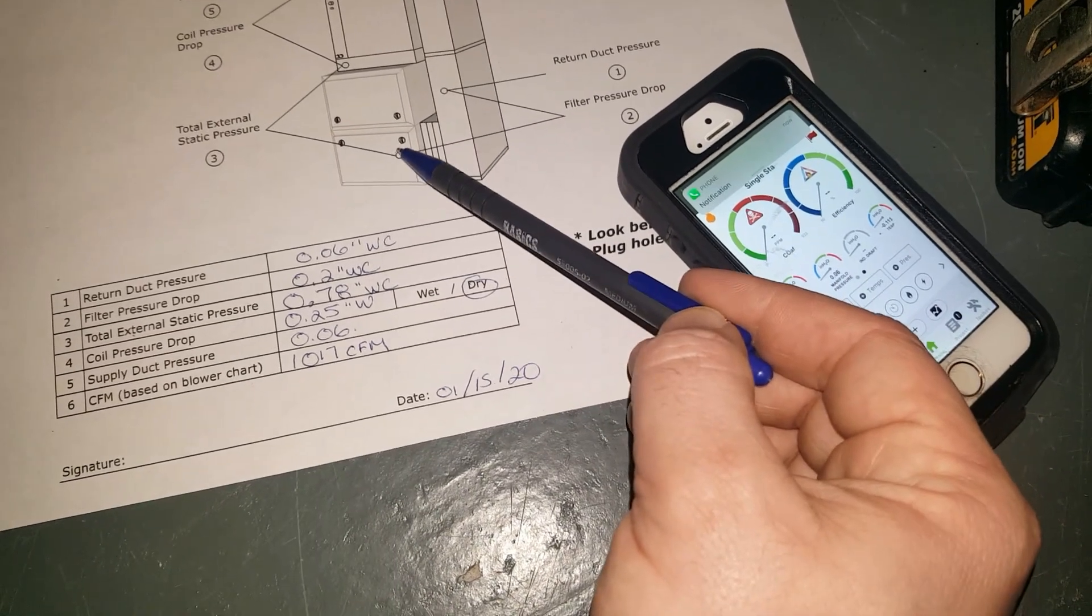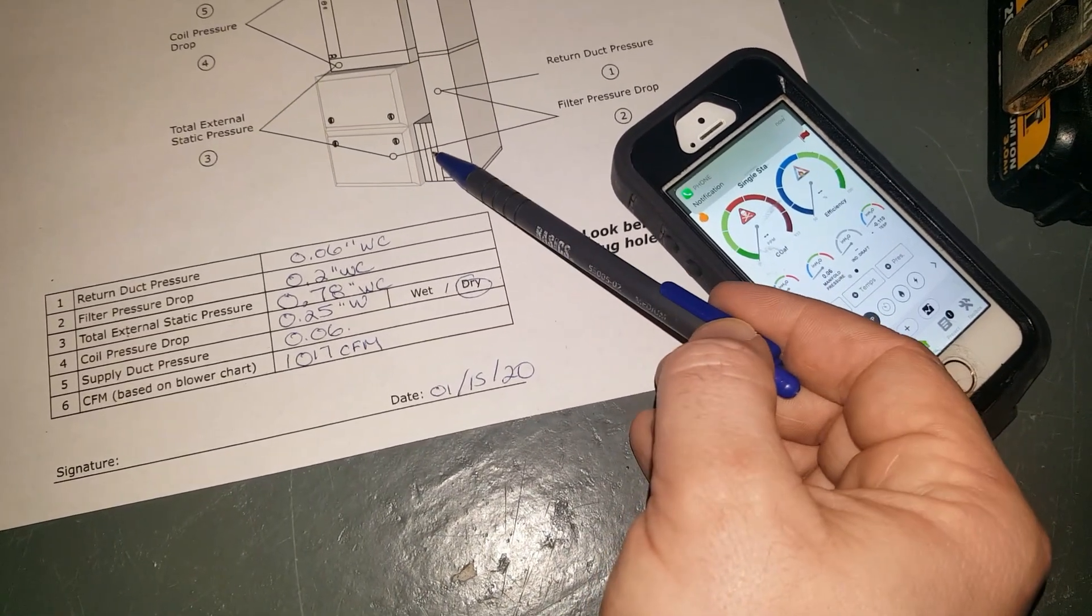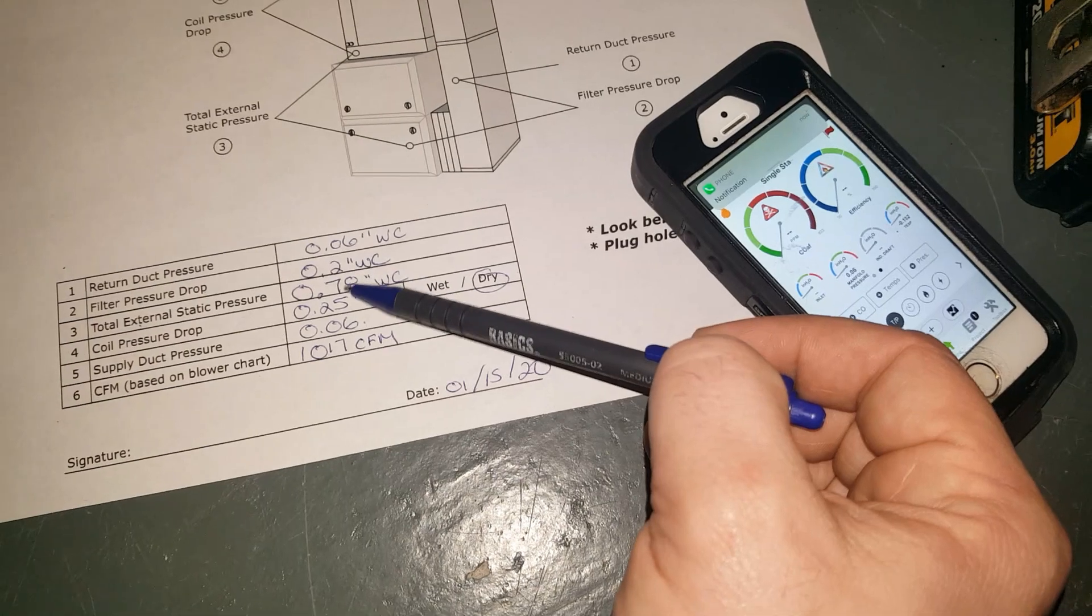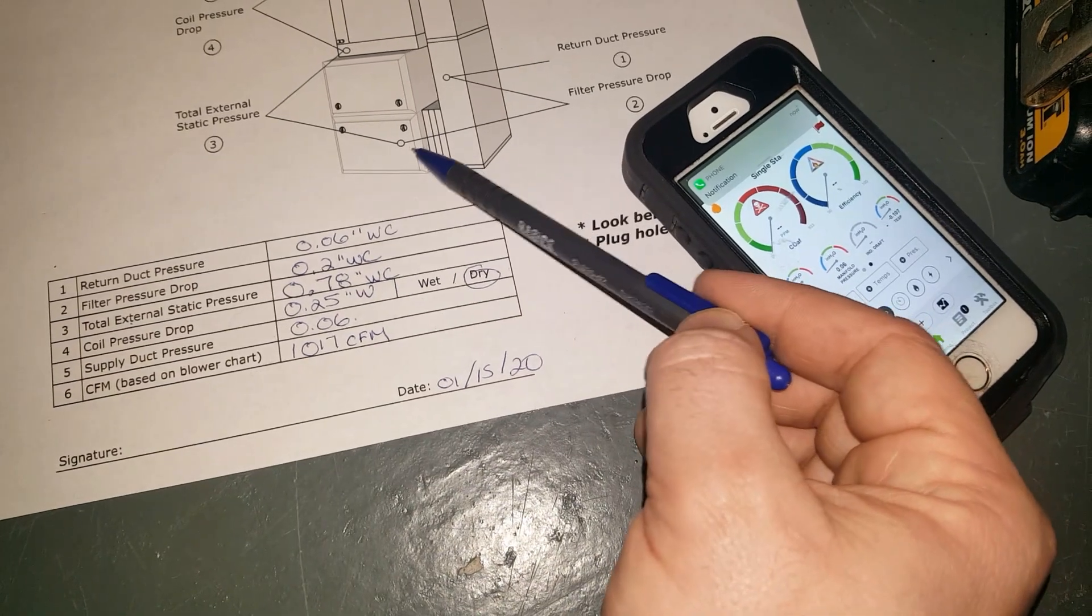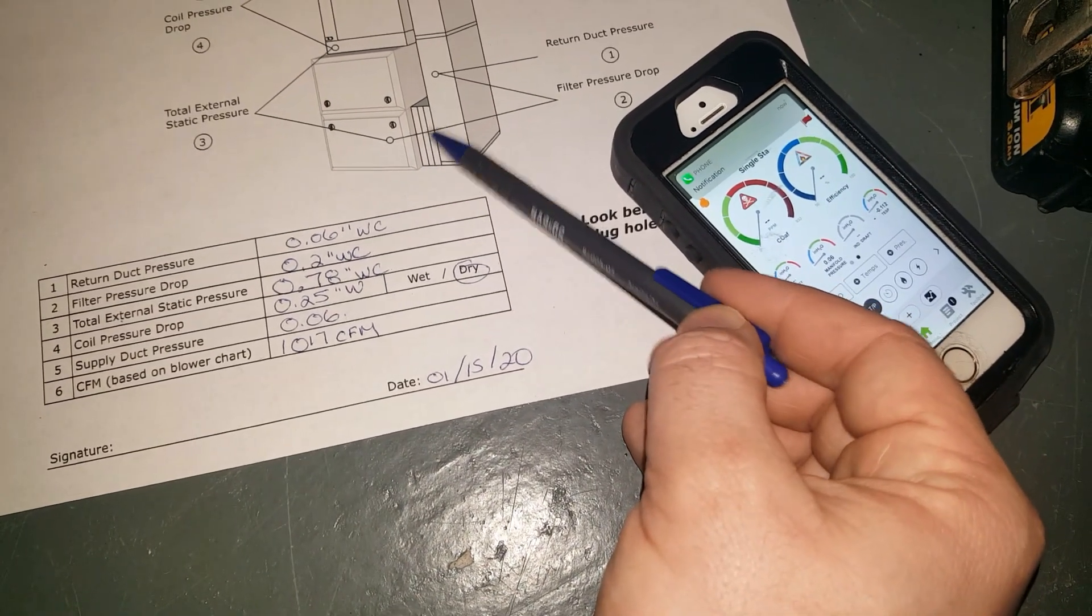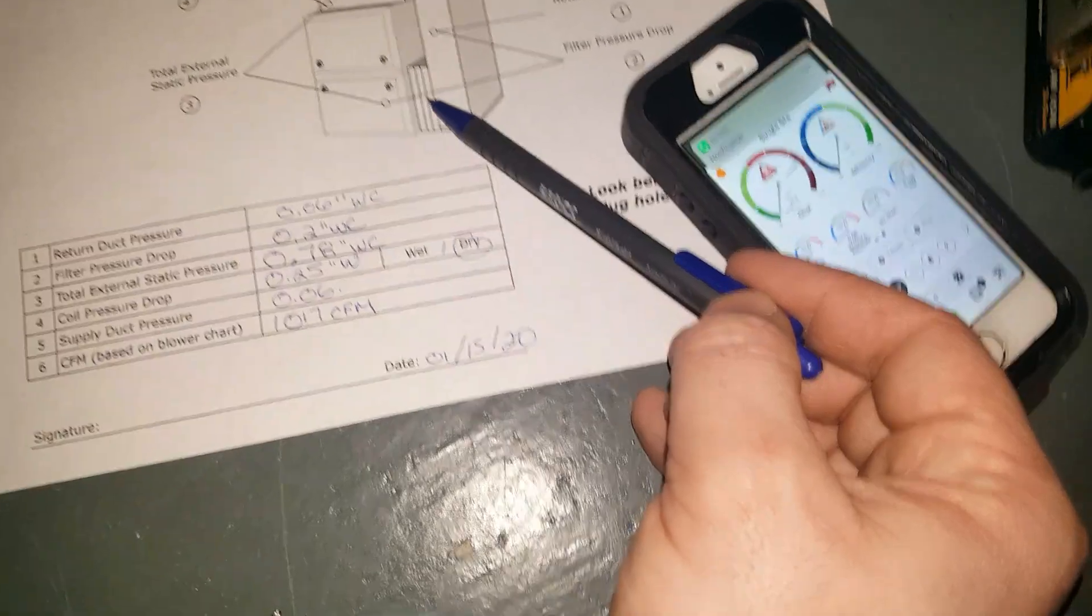Another quick check is your filter pressure drop. If we get there and we see a very high pressure drop, then you know your filter is starting to get dirty.